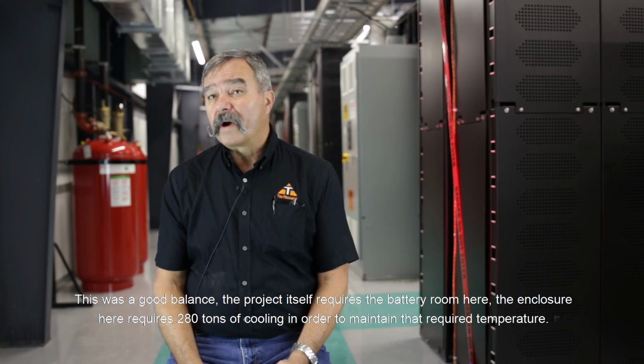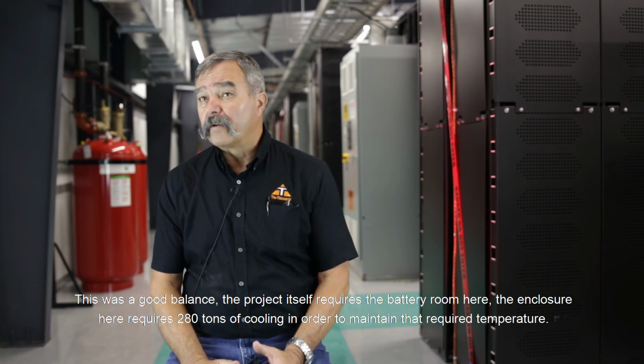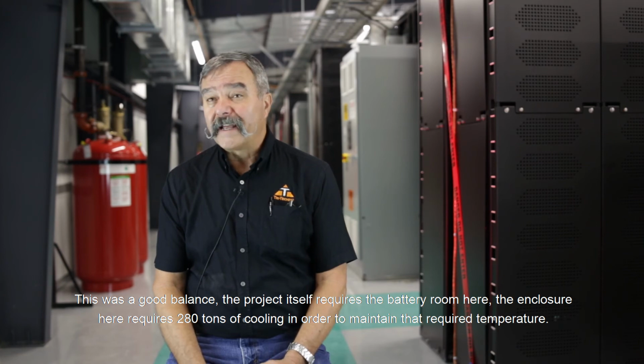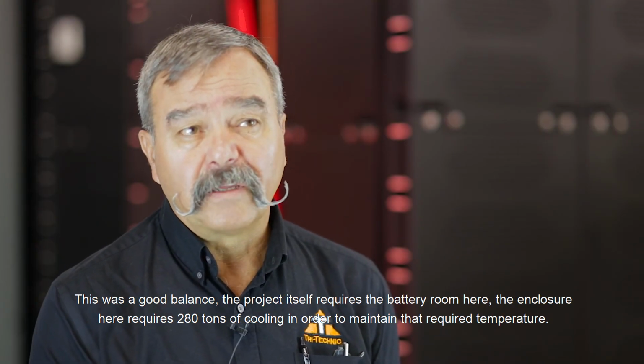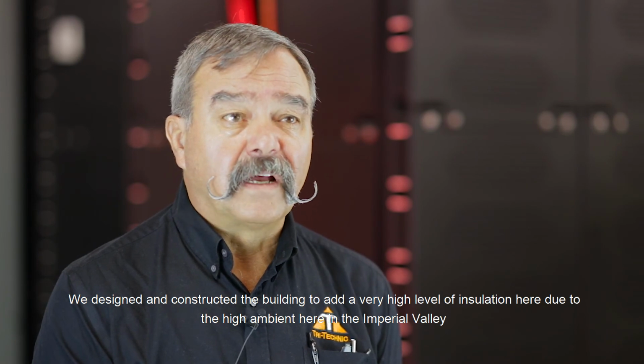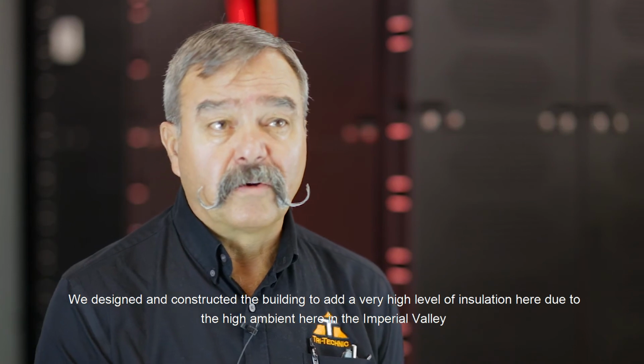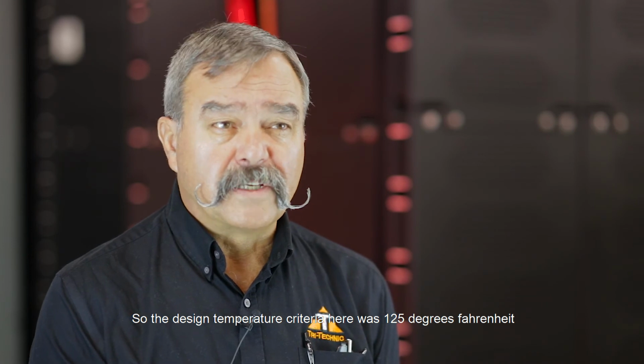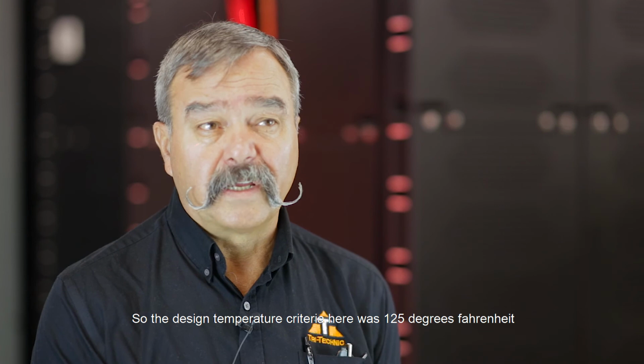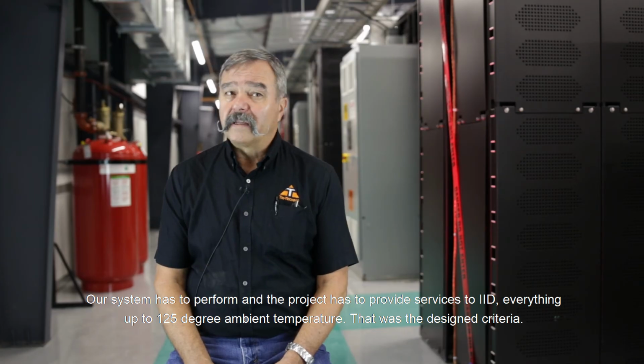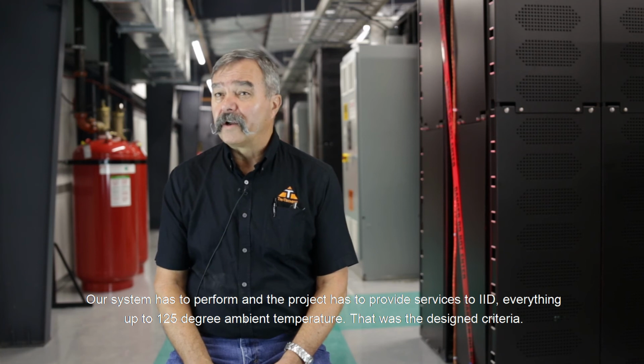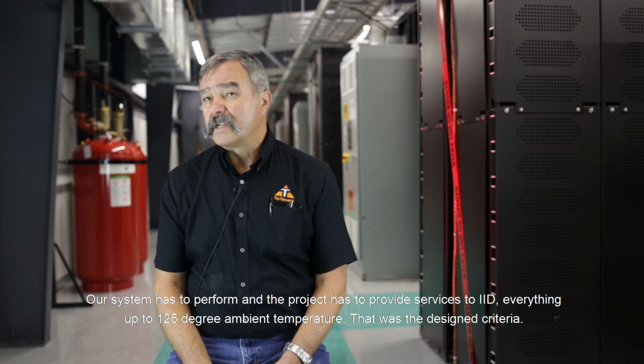The battery room enclosure here requires 280 tons of cooling in order to maintain that required temperature. We designed and constructed the building with a very high level of insulation due to the high ambient here in the Imperial Valley. It gets very, very hot here, as you well know. So the design temperature criteria here was 125 degrees Fahrenheit. Our system has to perform, and the project has to provide services to IID, at everything up to 125 degree ambient temperature. So that was the design criteria.